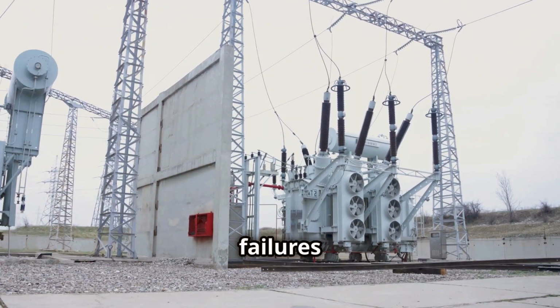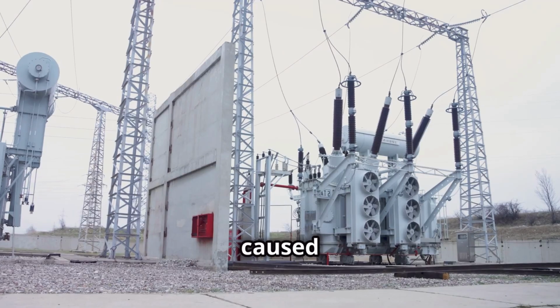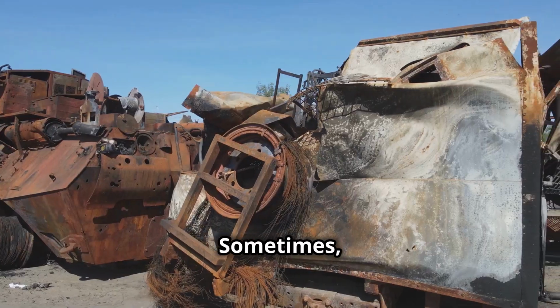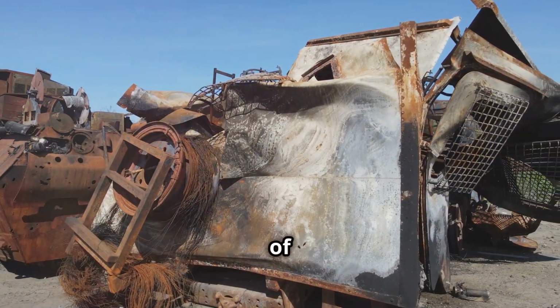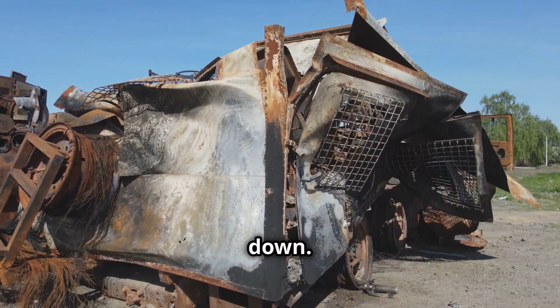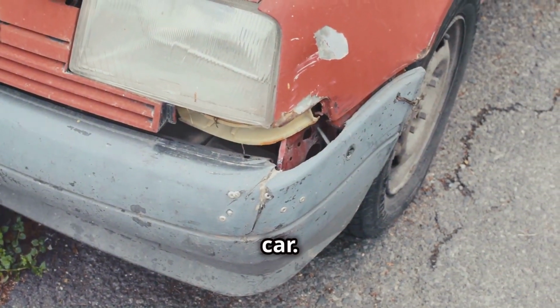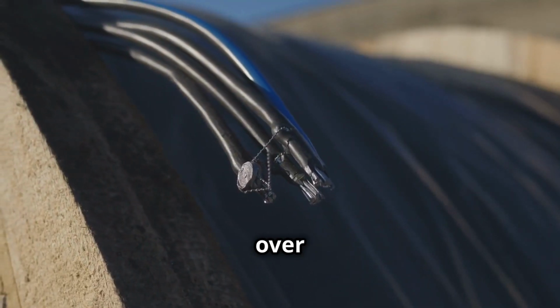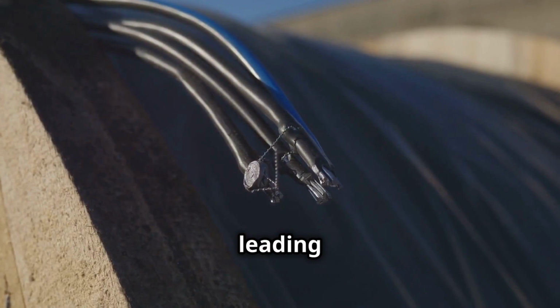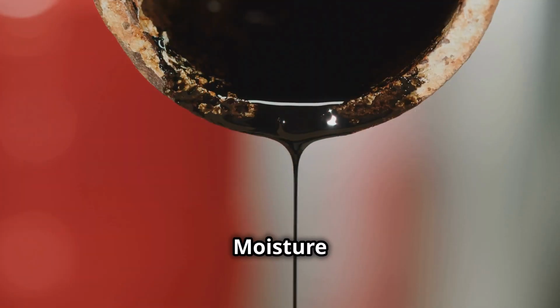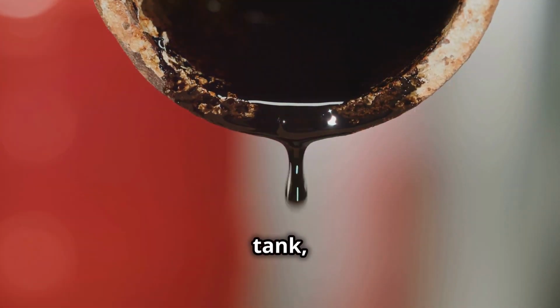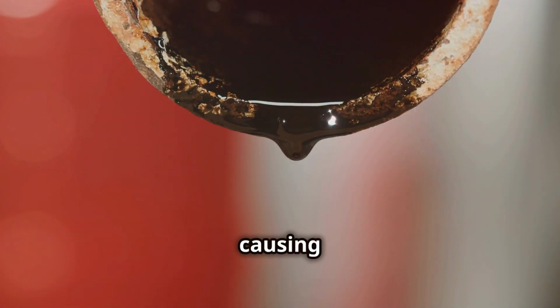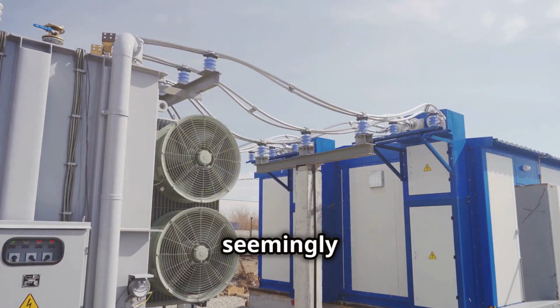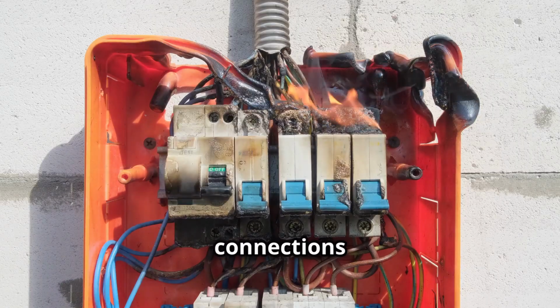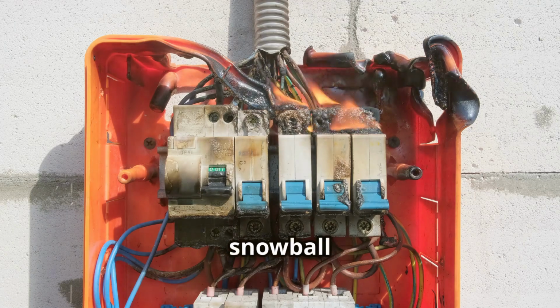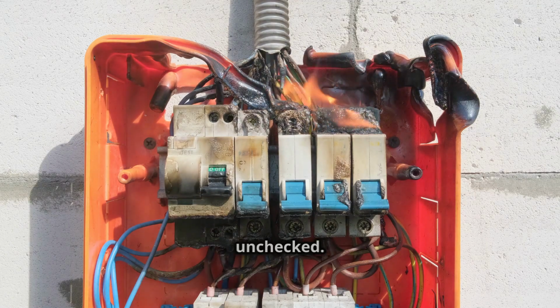But transformer failures aren't always dramatic explosions caused by natural disasters. Sometimes it's the slow, insidious creep of deterioration that brings them down. Think of it like rust eating away at a car. Insulation can break down over time, especially in harsh environments, leading to short circuits. Moisture can seep into the transformer's tank, contaminating the insulating oil and causing corrosion. Even seemingly minor issues like loose connections or faulty bushings can snowball into major problems if left unchecked.